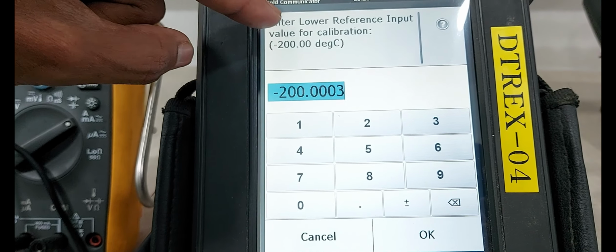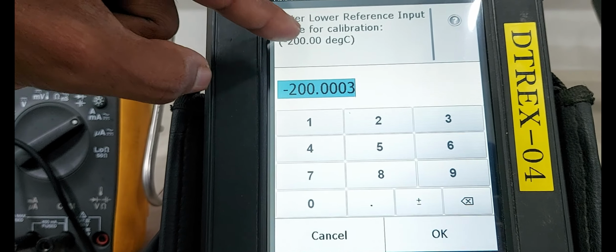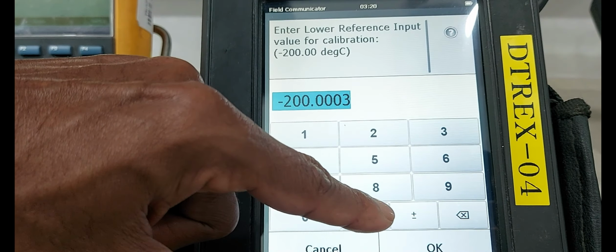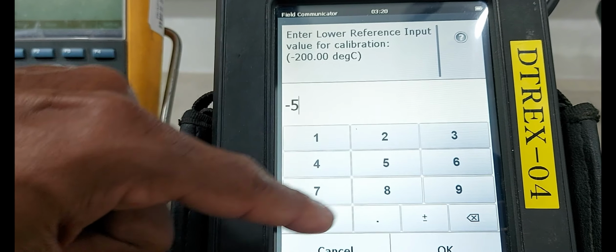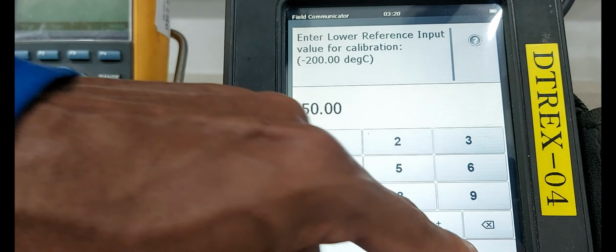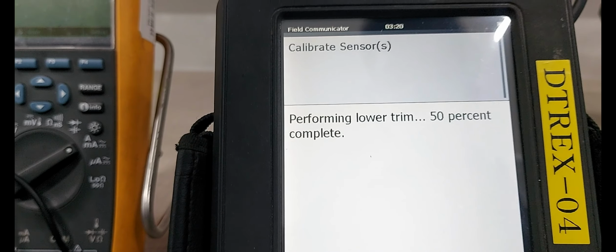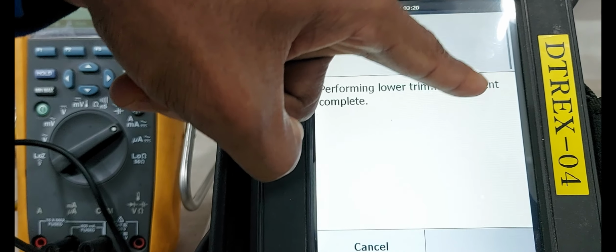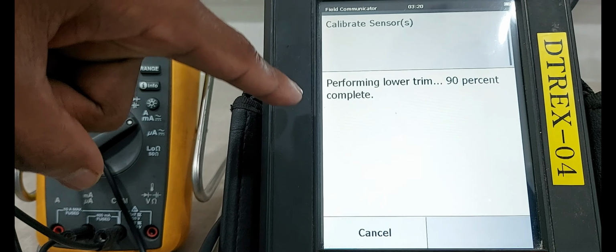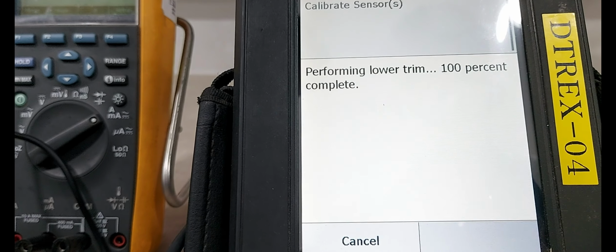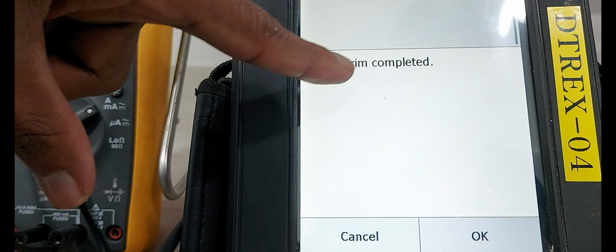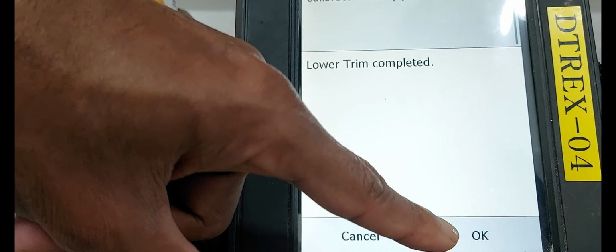Enter the low reference input value for the calibration. This value is -50 degree, -50.00 degree. Then okay. Now performing the lower trim, percentage base is 80% completed, 90% completed. Lower trim is completed. Then press OK.